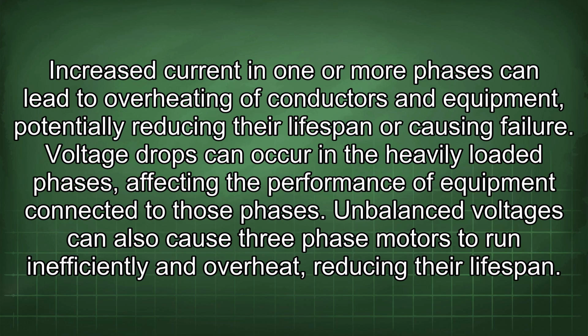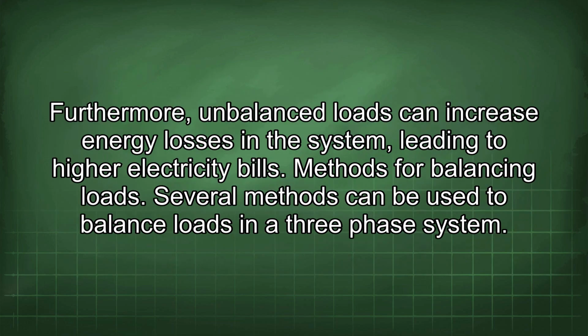Voltage drops can occur in the heavily loaded phases, affecting the performance of equipment connected to those phases. Unbalanced voltages can also cause three-phase motors to run inefficiently and overheat, reducing their lifespan. Furthermore, unbalanced loads can increase energy losses in the system, leading to higher electricity bills. Methods for balancing loads. Several methods can be used to balance loads in a three-phase system.